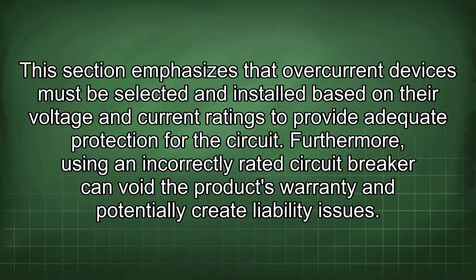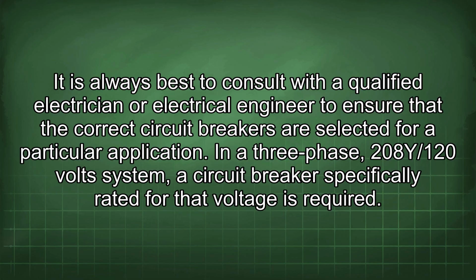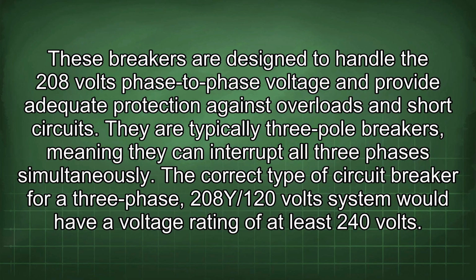Furthermore, using an incorrectly rated circuit breaker can void the product's warranty and potentially create liability issues. It is always best to consult with a qualified electrician or electrical engineer to ensure that the correct circuit breakers are selected for a particular application. In a 3-phase 208Y/120 volts system, a circuit breaker specifically rated for that voltage is required. These breakers are designed to handle the 208 volts phase-to-phase voltage and provide adequate protection against overloads and short circuits. They are typically 3-pole breakers, meaning they can interrupt all 3 phases simultaneously.